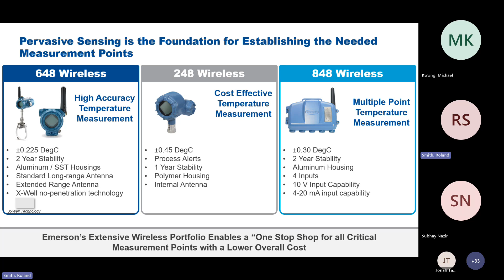A little bit on the X-Well technology. Again, this is part of our pervasive, non-intrusive temperature measurement, where traditionally, when you design a thermowell, there's a whole bunch of considerations you have to take into effect. You know, your thermowell length, the mounting style, material, wake frequency is a huge one. So wake frequency, for those that may not know what that is, we do a wake frequency calculation to determine how much force of flow, based on viscosity, pressure, and flow rate, of course, before that thermowell may be in jeopardy of breaking off.